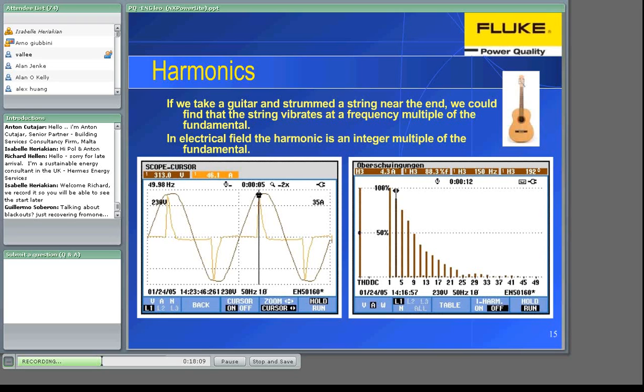The harmonics content is represented by a bar graph, as you can see on the right side, called frequency spectrum. Any cyclical waveform function can be divided into a sinusoid at the fundamental frequency plus another. This mathematical procedure used to break down the harmonic content is called Fourier transformation. In case you have the possibility to connect a power analyzer to the power supply of your AC PC, very probably you will be faced with the same results that you see on the screen.